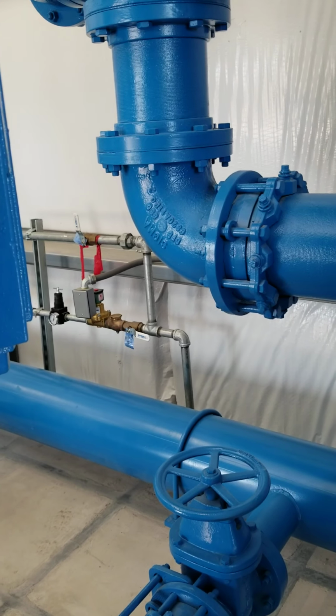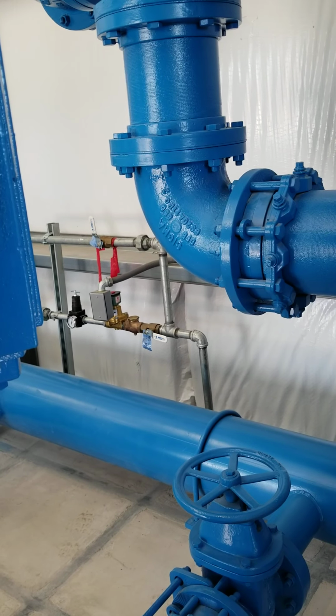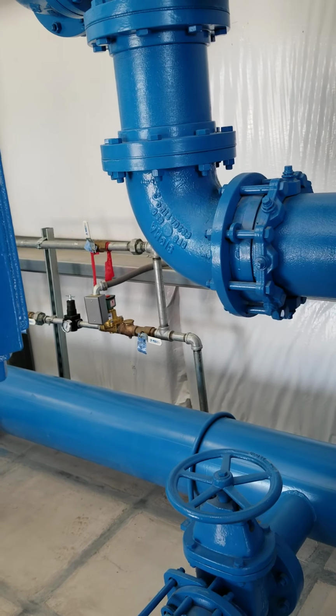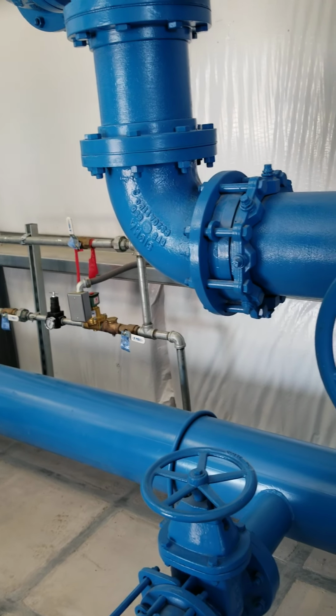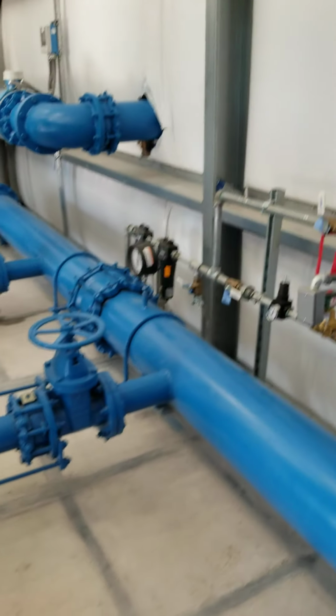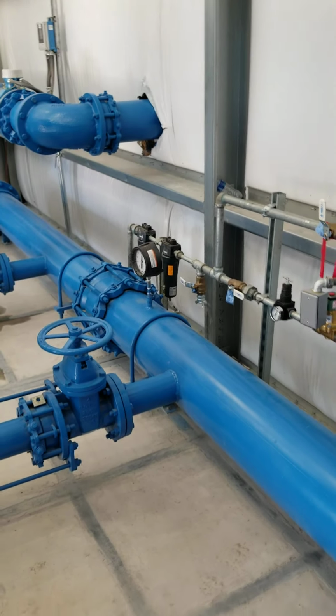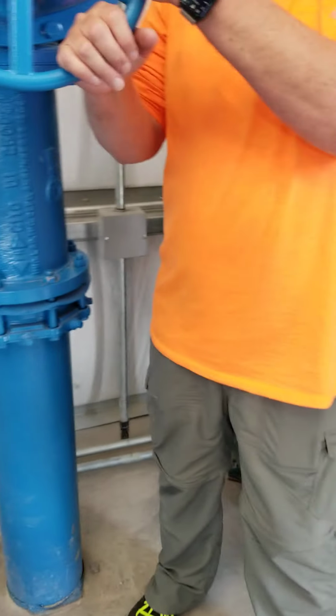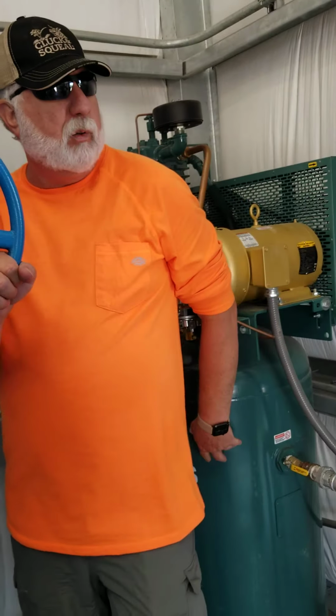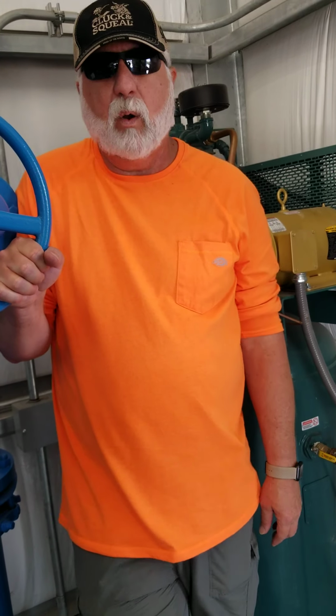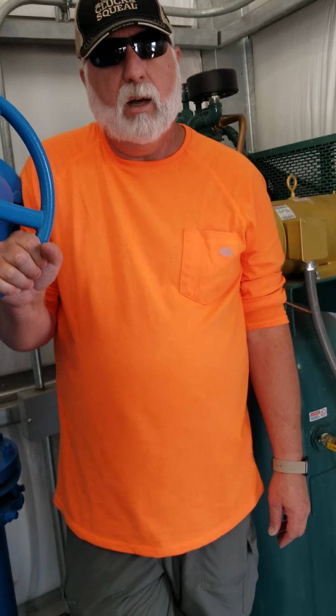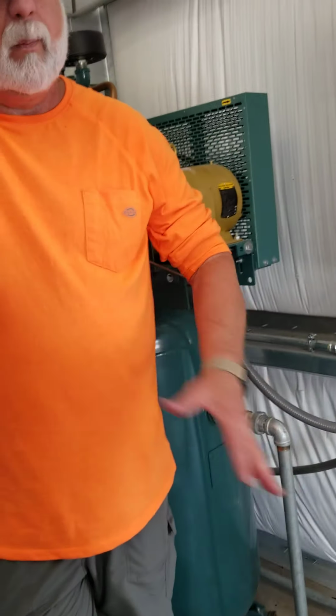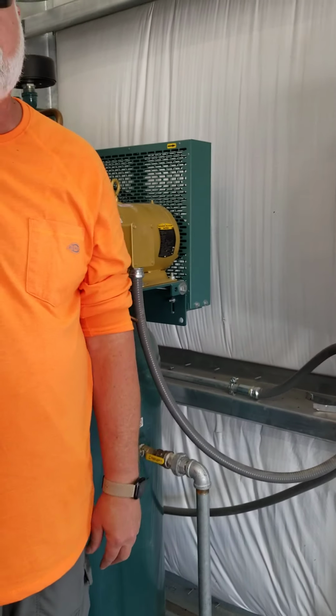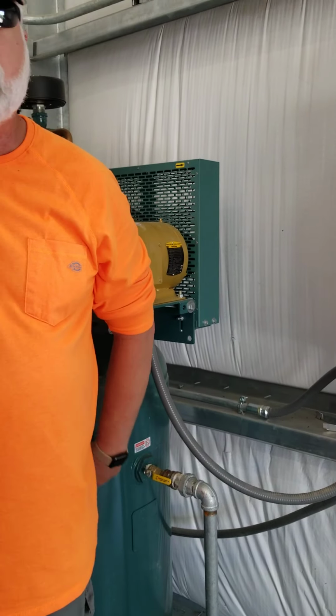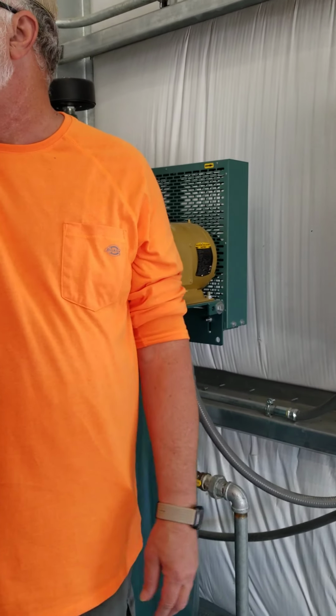You also have 2 air filters over there. One's a particulate filter, the other's a coalescing filter to take whatever oil carryover might be from the air compressors and take it out of the air before it gets to your hydro tank. These compressors are filled with a food grade synthetic oil. So that also helps protect your potable water system from any contamination and the fact that it's food grade oil. And then you've got the 2 filters.